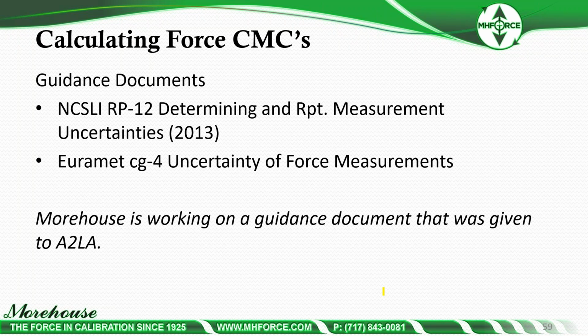So guidance documents, we're getting into the CMC section. Guidance documents that are available, you have NCSLI RP12. That's going to do nothing for you as far as ISO 376 is concerned. It's just there. I recommend it. And you have Euramet cg-4, which I quoted earlier in the one section. I highly recommend, free to download. Anybody should read Euramet cg-4 if they're doing ISO 376 calibration. It's very, very complete. It may even be overly complete, but it's a fantastic document. And then we're working on a guidance document that was given to A2LA. Our guidance document has 4 cases.